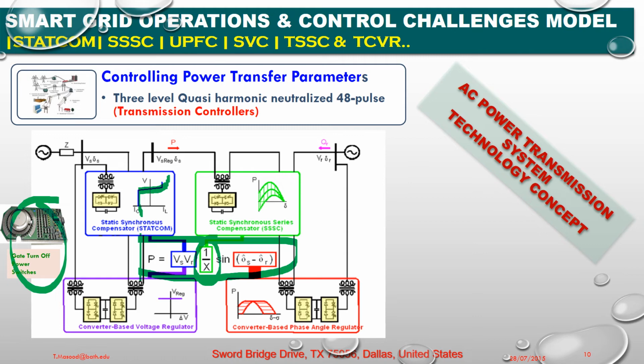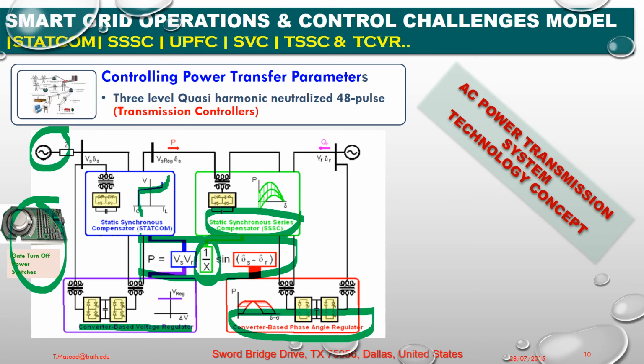Both operations it demonstrates. Okay, the converter-based voltage regulator is the first device here in order to adjust the voltage. Okay, so this is my second phase here. To adjust the line reactance, we are using a static synchronous series compensator, that is SSSC, to reduce the line reactance or line impedance in order to deliver maximum power. Okay. To adjust the power angle, I am using here the converter-based phase angle control. This is my sending end, generation side, and this is my load side, receiving end. So that is how the 3-level quasi-harmonic neutralized 48 pulse modulations are working in order to deliver the required results.